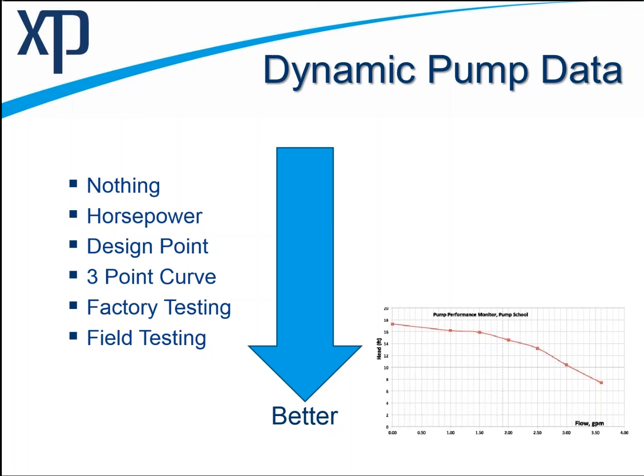So you may have a pump where you add that pump, and remember the pump's in parallel, you add the pump and actually no extra flow happens because the system curve raises up to a high enough head that just shuts that pump off. You see this a lot with mis-sized pumps, so you have two or three pumps that are not the same, and one of them operates at a lower head, and so when the first one turns on, the second one never turns on, just can never produce any kind of flow.